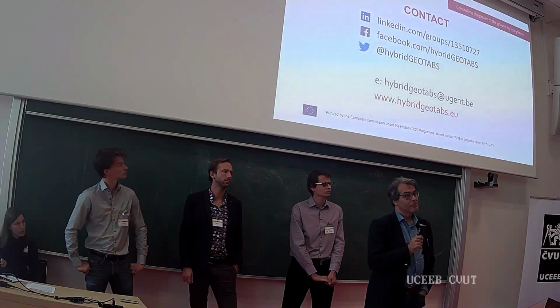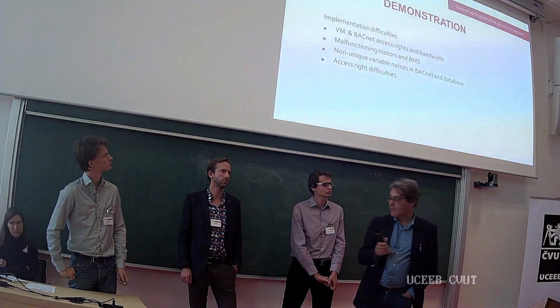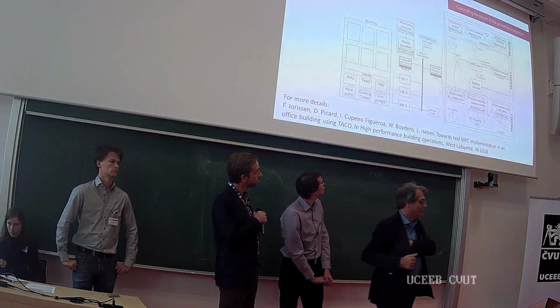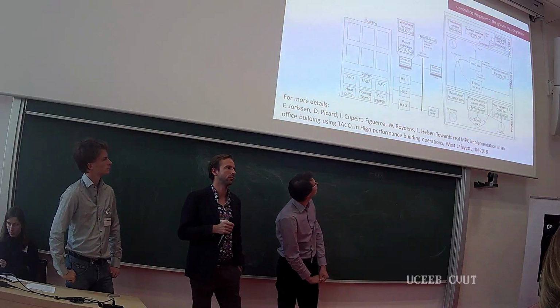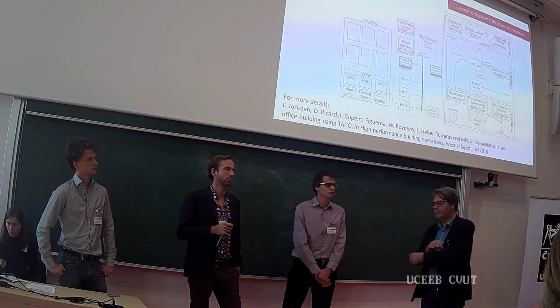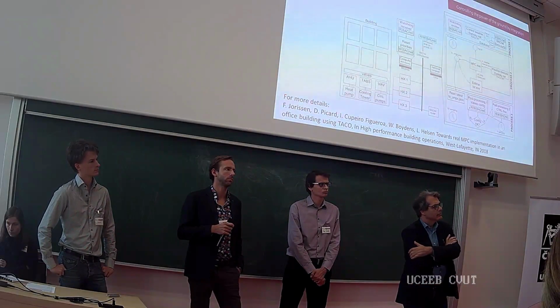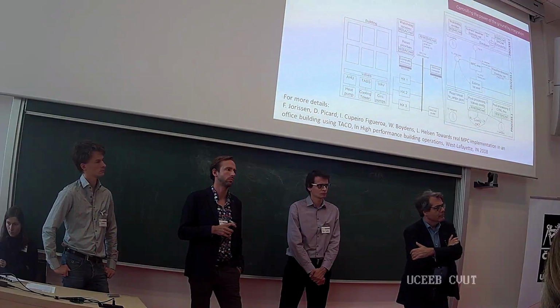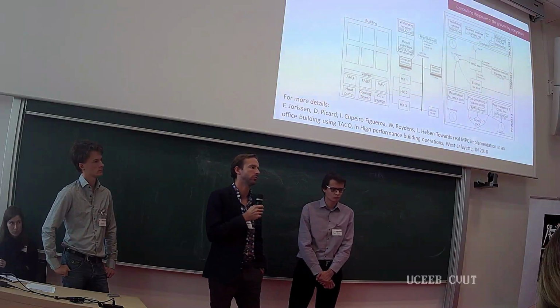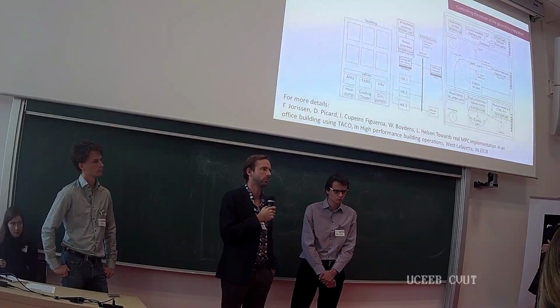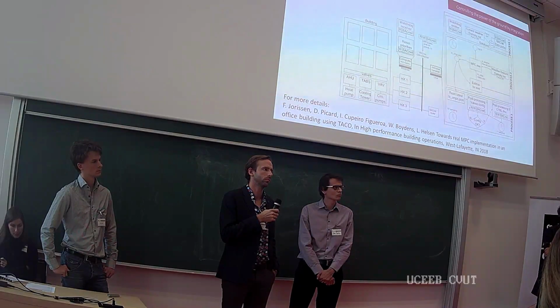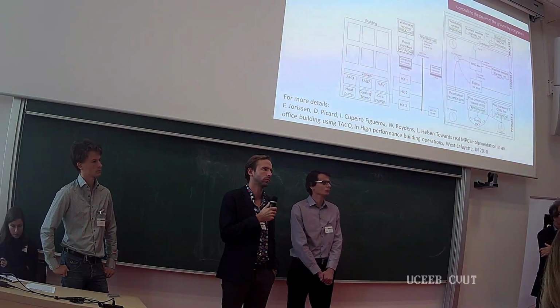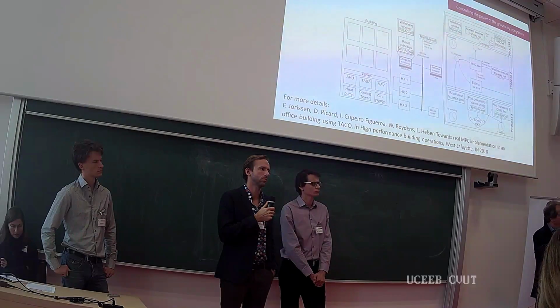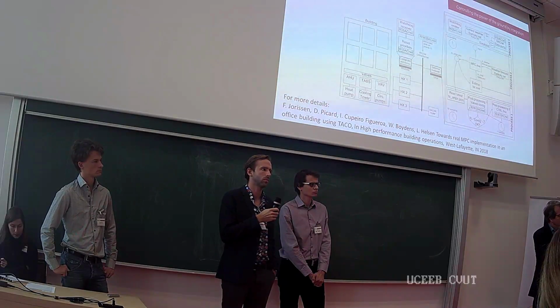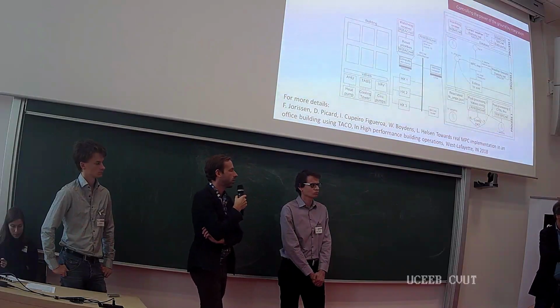You showed something that could be seen as hierarchical control, with an MPC on a 1 hour period, and below that some low-level controllers on 15-minute and 1-minute periods. My question is how you decide what should be controlled by the MPC and what should be done by the low-level controller. On one hand you'd like to take into account all parameters in the optimization, but on the other you can end up with an infeasible model or something not feasible in real-time operation. Do you have general guidelines, since each building is individual, and perhaps one outcome should be some guidelines for deciding this distinction between higher and lower level?